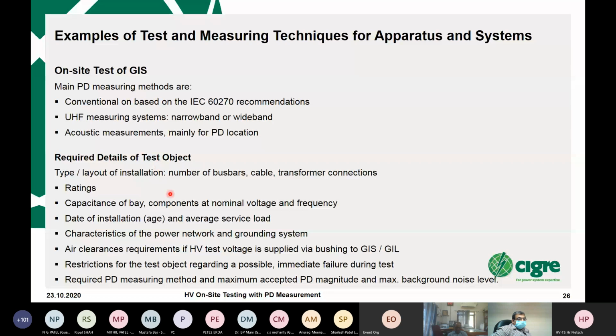Again, the required details of the test object. It's very important, again, for the power you need. That means for the test source, you have to bring on site how to connect or switch the different substations, single phase, 3-phase. If it's a really big one, then it's very tricky to measure it with a very simple test system. You have to disconnect some of the bays and so on. And you have to get information on what you are testing. It's very, very important. So try to get the files about the equipment you would like to test. Had some outages, were some parts repaired and so on, or ask those who know this.